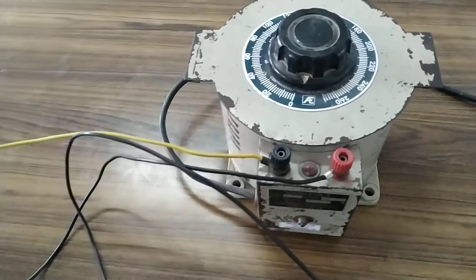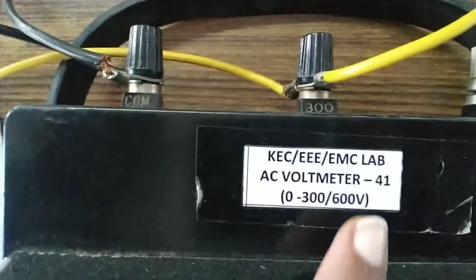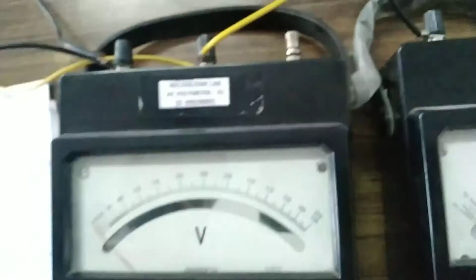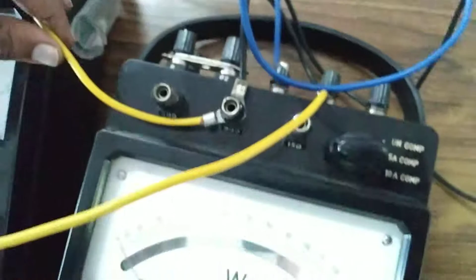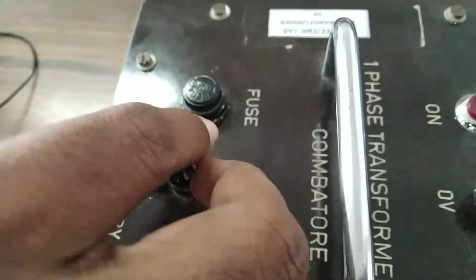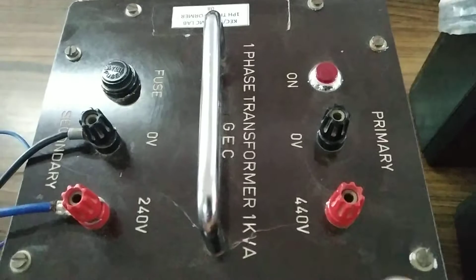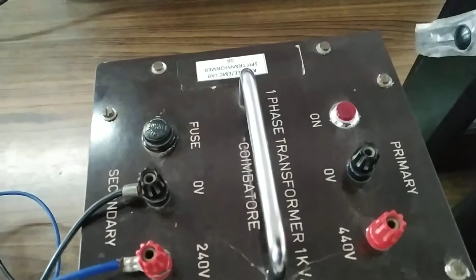Now we see the neutral connection. From the neutral, connection is given to the 300 voltage terminal in the voltmeter. Again from the same 300 voltage terminal, connection is given to the 300 voltage terminal in the wattmeter. Again from the 300 voltage of the wattmeter, connection is given to the neutral of the LV side, that is the neutral in the transformer. You leave the HV side open, you don't need to do anything on that. These are all the connections. We leave the HV side open because it is called the open circuit test.